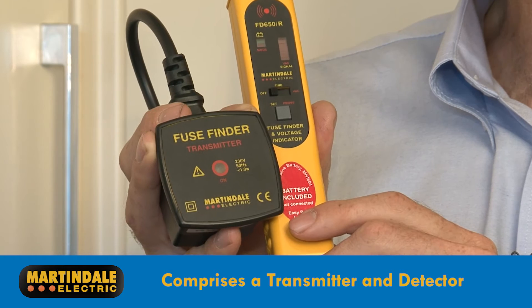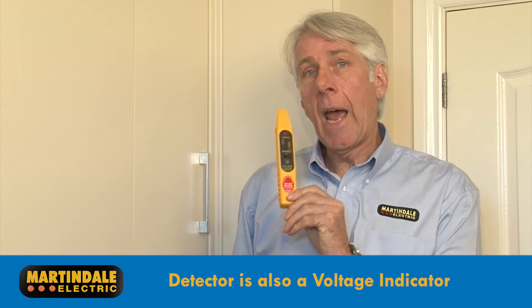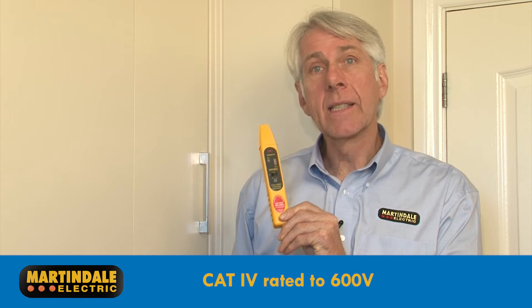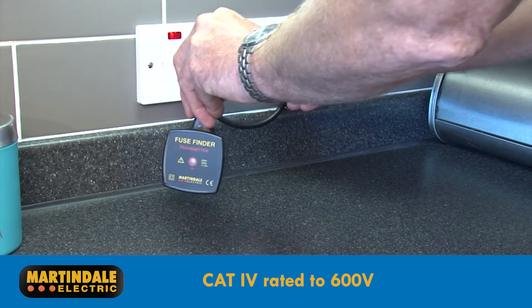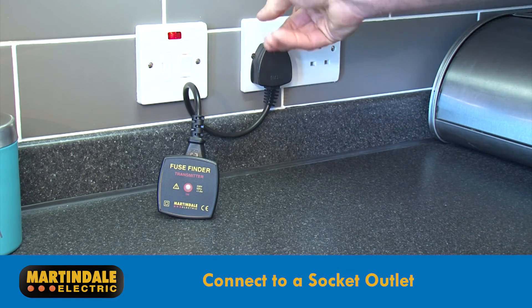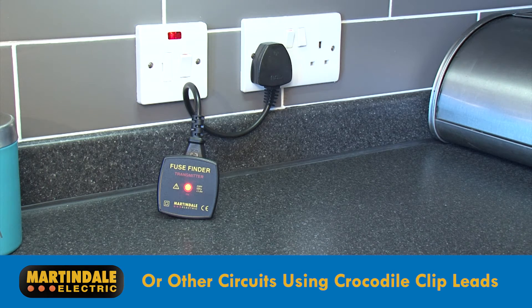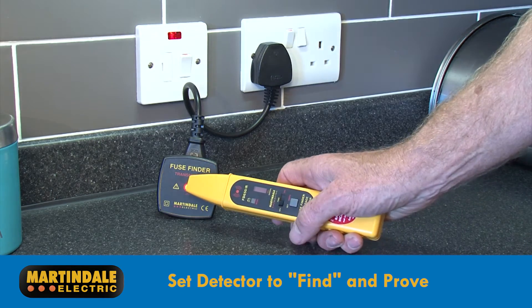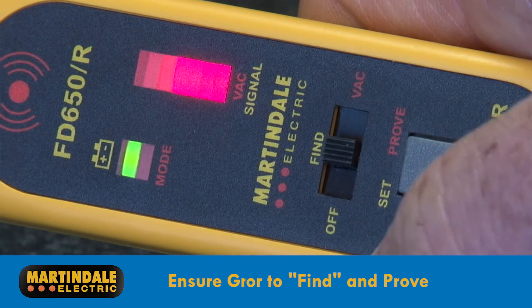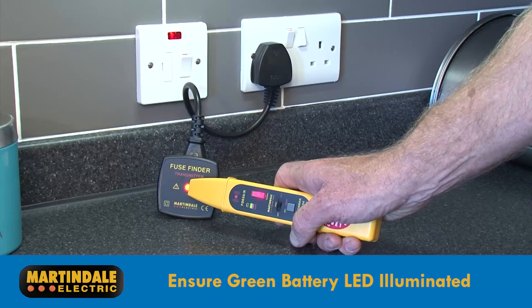The FD650 comprises of a transmitter and a detector, which can also serve as a handy voltage indicator and is Cat4 rated to 600 volts. The transmitter can be connected to either a socket outlet using the plug provided, or to other circuits using the crocodile clip leads. Once the transmitter is connected and working, the detector can be set to find and prove against the transmitter. It's important to ensure that the green battery LED is continuously illuminated.